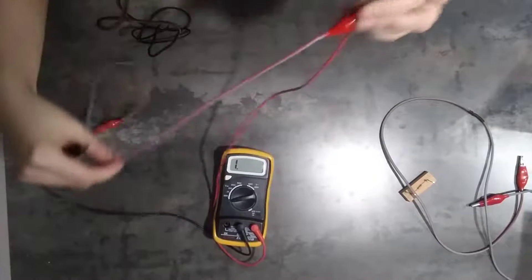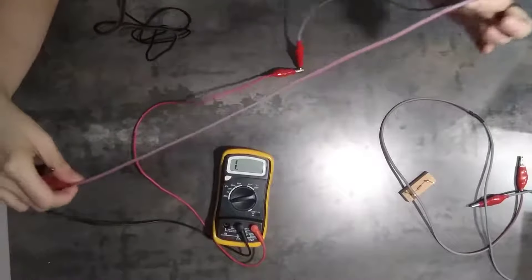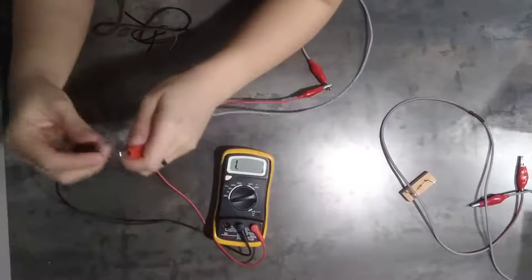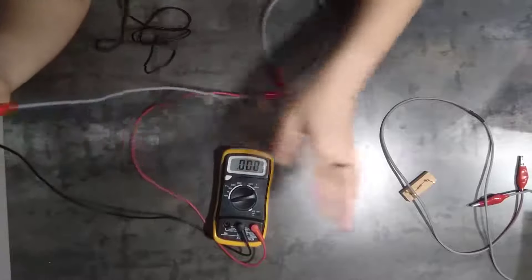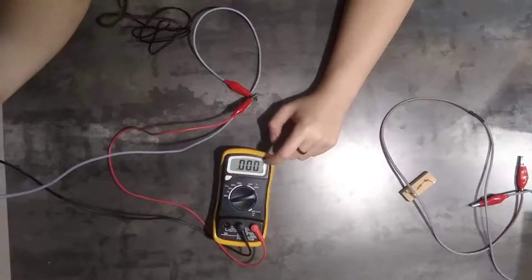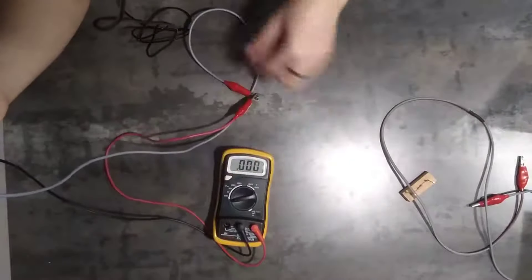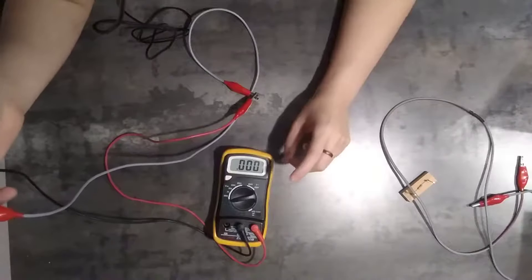So if you connect this directly to a connecting lead like this, I connect this one this way. This one is the wire. I connect it this way. We should get a reading of 0. Why 0? Because connecting wire, the gray connecting wire should not have any resistance.